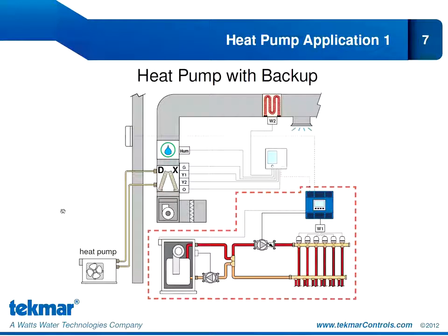Our first heat pump application is a very common application where we're using an air-to-air heat pump to provide forced air heating and cooling. We've also shown the option of adding the radiant system, and since it is optional, we've outlined it in a dashed red line. If we include the radiant, that is our first stage of heat. A second stage of heat would be provided by the heat pump. If it's a 2-stage heat pump, we would get our third stage of heat from the heat pump as well, and that would be through the Y1 and the Y2 relay connections. If needed, we can bring on electric strip backup as a 4th stage of heat through the W2 relay connection. We've shown the fan operation with the G relay connection, and we're controlling humidification with an accessory relay connection. In cooling mode, our heat pump can provide up to 2 stages of cooling if it is a 2-stage heat pump. So this is a 4-stage heat, 2-stage cool heat pump application.